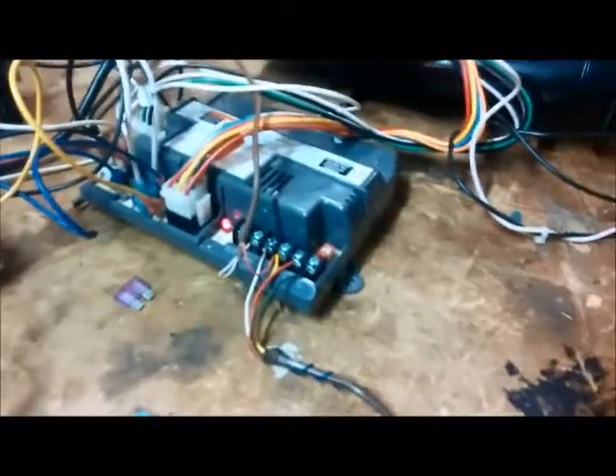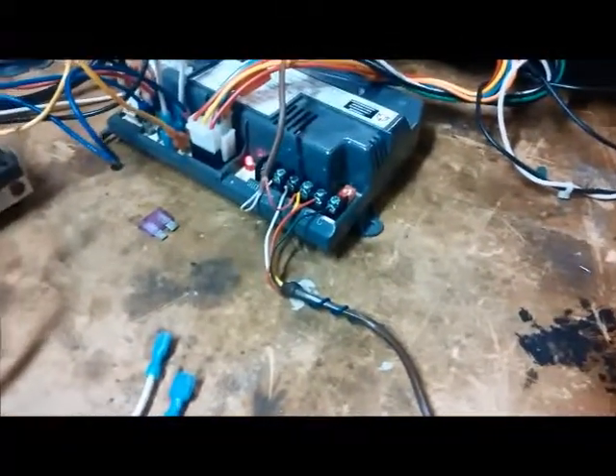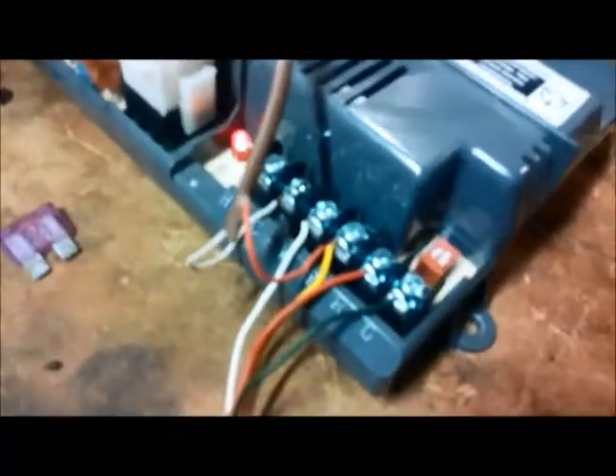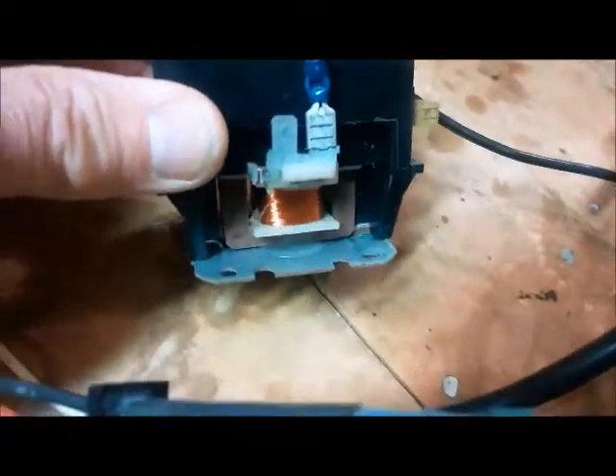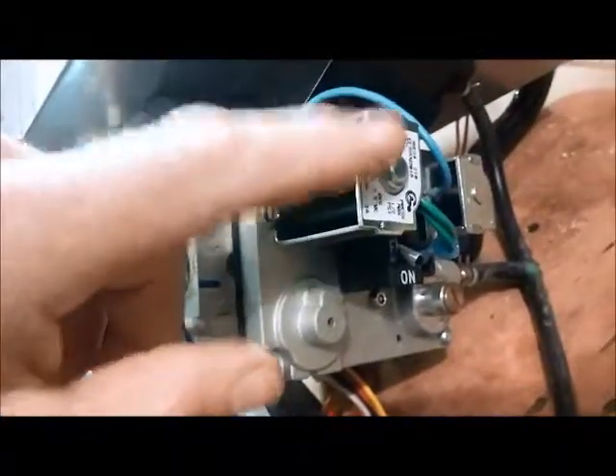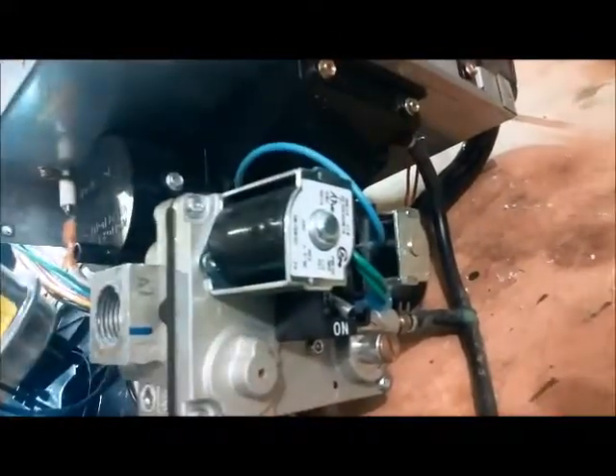So like I say, that's short. Could be inside a component. You know, we shorted R to C. R has to go through something and do work. Either the coil on the contactor at the air conditioner, or the coil on the gas valve. Right there, that would do work. And once you put 24 volts across the gas valve, in other words, a W call, that's going to pull this coil in and open the gas valve and allow gas to go to the burners.